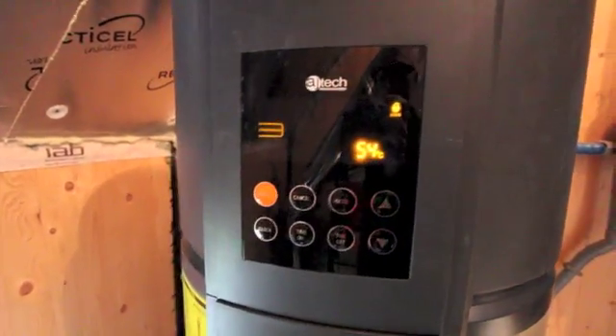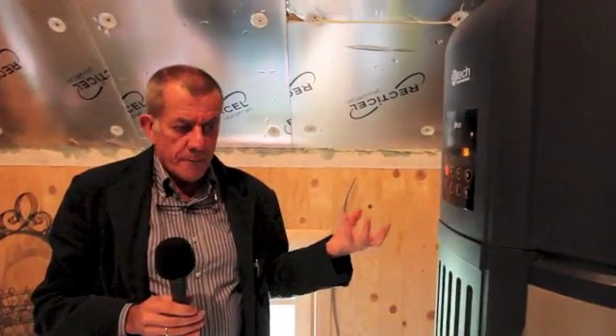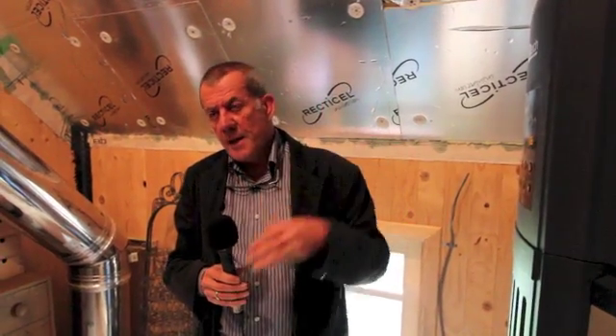The air heat pump is not connected to the outside. It takes advantage of the warm air in this room produced by the chimney conduit. Benefiting from this heat, the output of the heat pump is increased, but the cold that it produces also cools down the room in which we are standing. Thus, in short, if the heat pump wasn't here, it would always be very hot in the room due to the heat produced by the chimney conduit. The heat pump kicks in to absorb a major part of this heat to increase its output, and if the heat pump is not working, the heat produced here in this room is recycled by the vent opening and redistributed throughout the house.